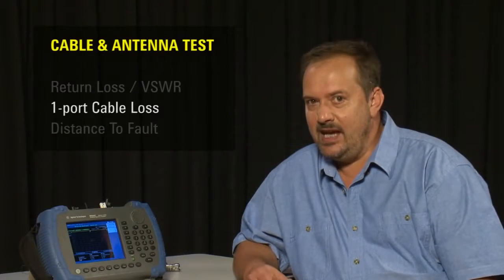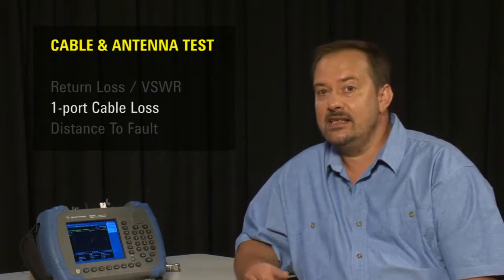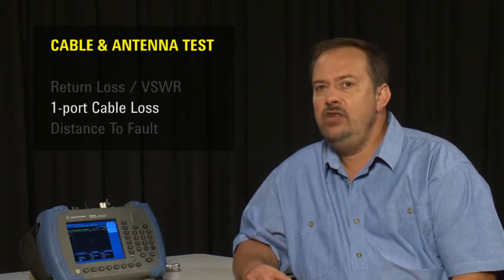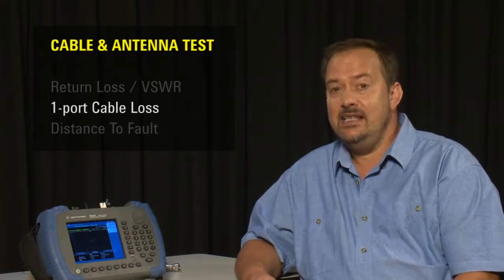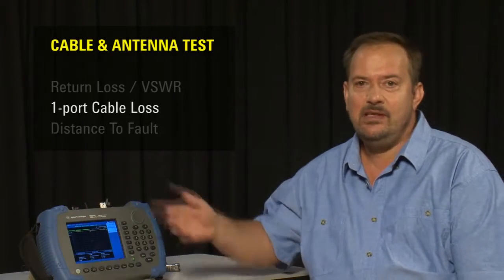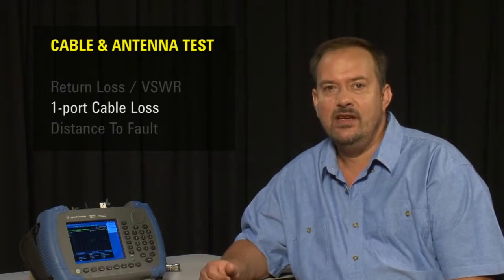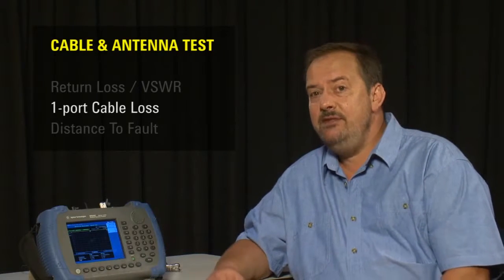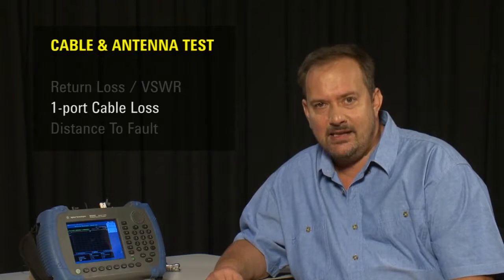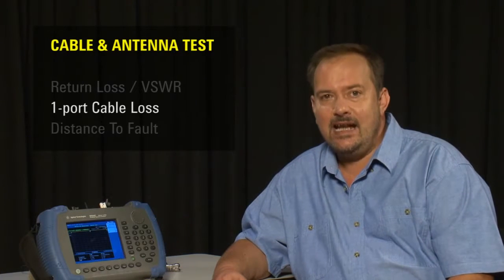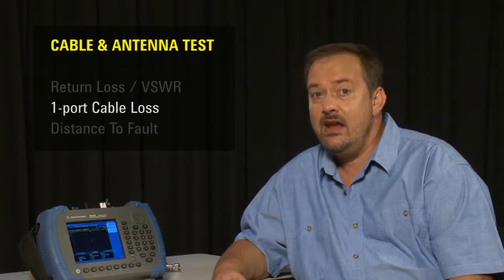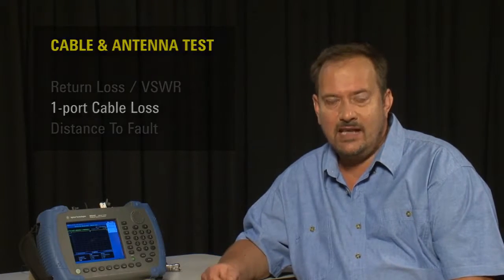If you can access both ends of a cable, for example when it is still on its cable reel when new, then you do not need to use this feature, as the HSA's tracking generator can be used to make a standard two port measurement of insertion loss. But if your cable is already installed on a mast, then this feature is extremely useful, as it allows us to measure the cable's attenuation from just one end of the cable.